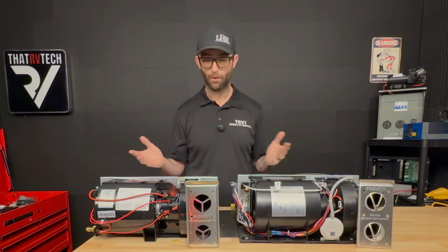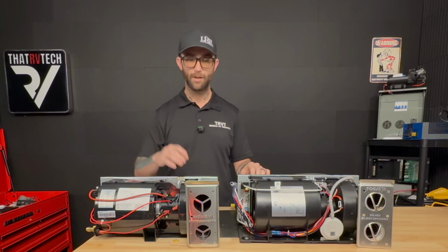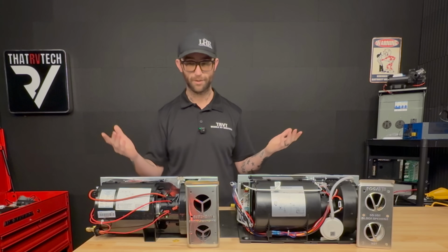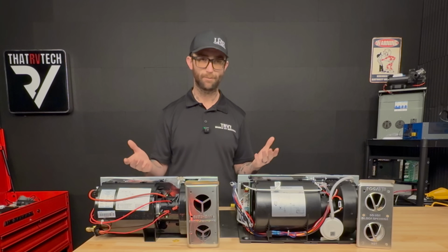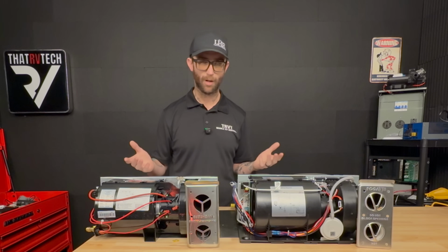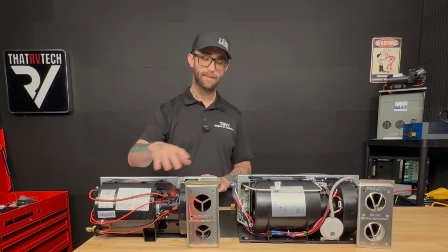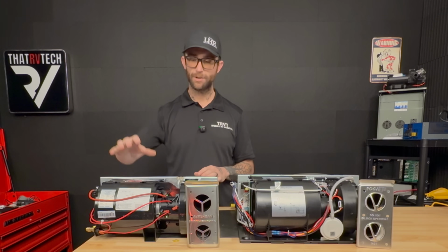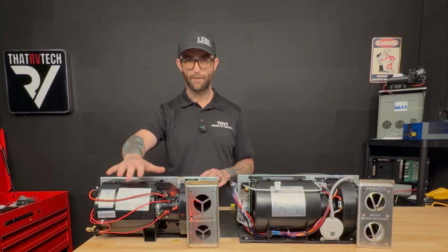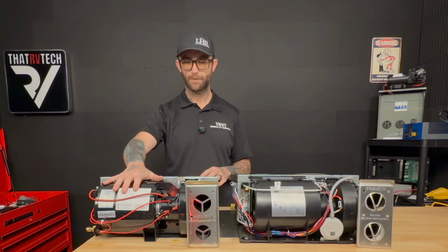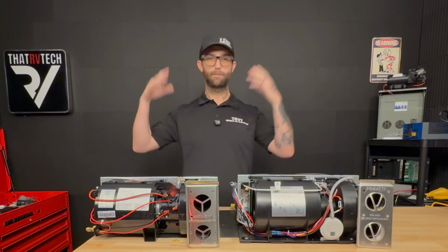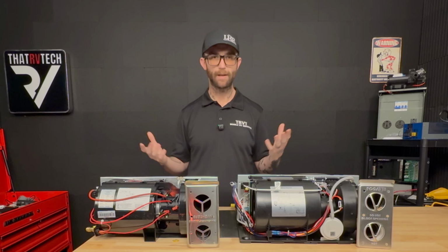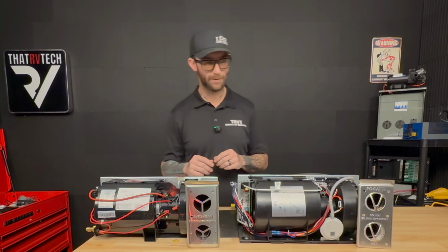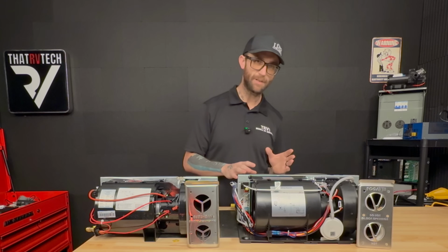Let's talk about how the Suburban currently does it. You have that sail switch, again, which is a cheaply made part and can easily be defeated by a little clump of hair. But that sensor, if you will, or switch, is on the blower side. This is the side of the furnace that takes the warm air on the heat exchanger and blows it backwards into the RV, if you will, in layman's terms. Now, again, I told you that that was a safety switch.